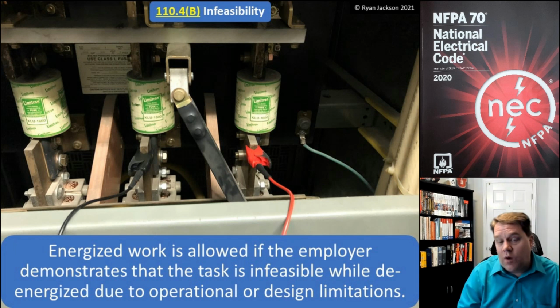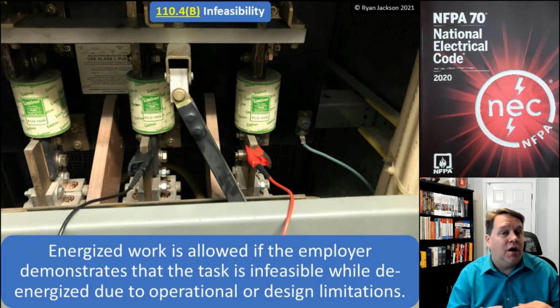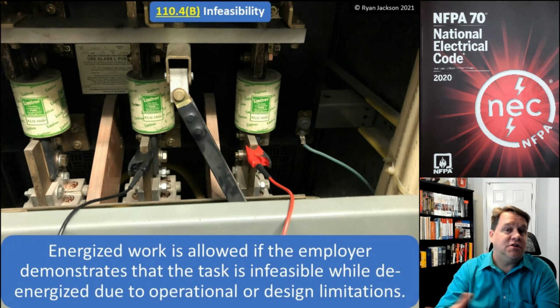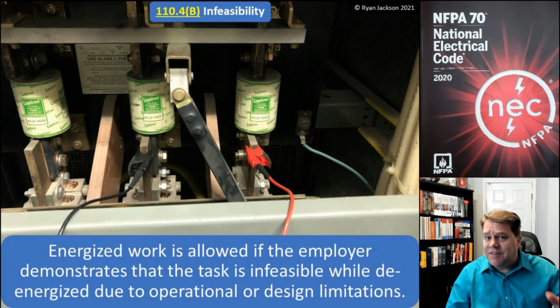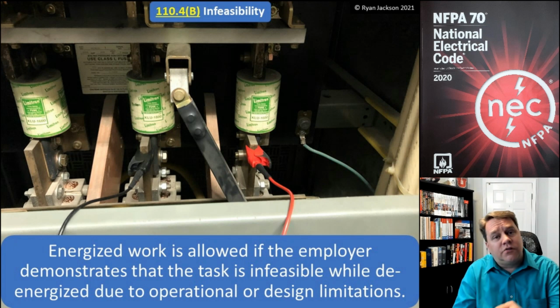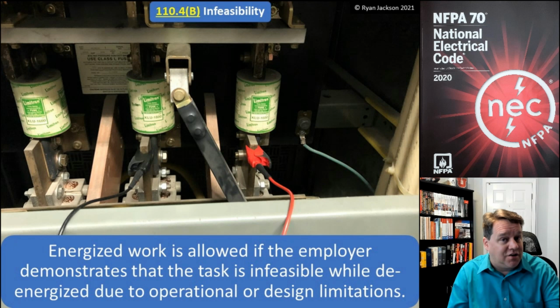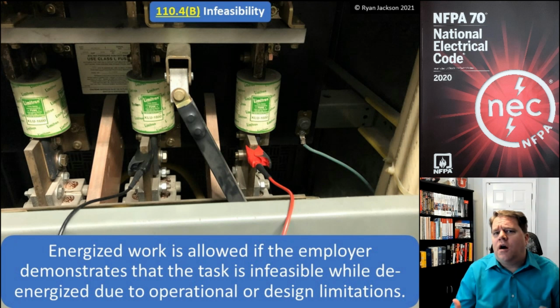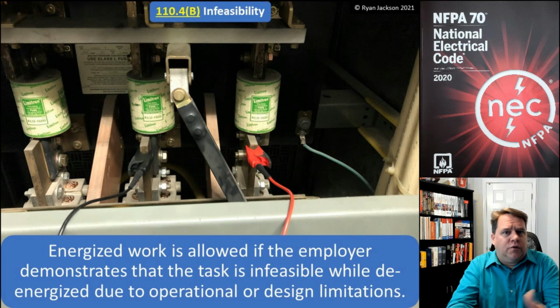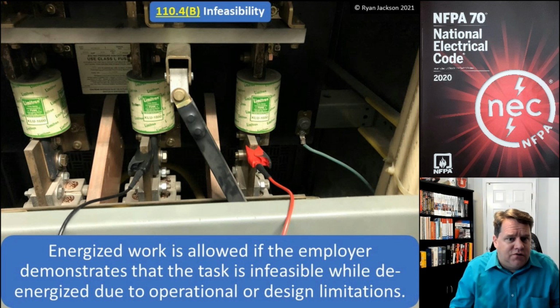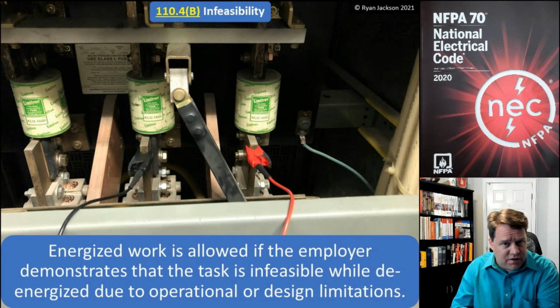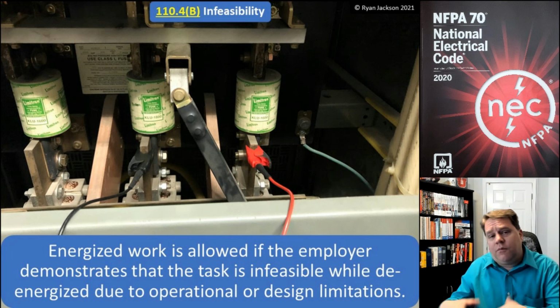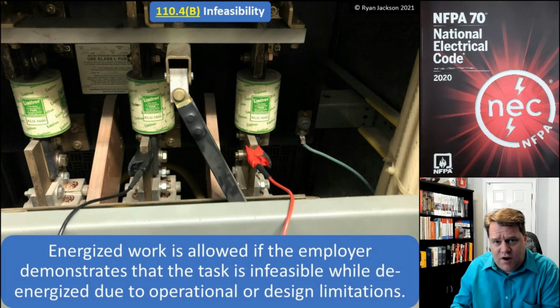And when we look at the Article 100 definition of working on energized equipment, it breaks it up into two different types. It talks about repair on energized equipment, which is where I'm actually going in and physically making changes and terminations and things. That can usually be avoided. The other type of working on energized equipment is diagnostics. And unfortunately, we're not in a position where we can verify voltage without things being turned on. So I think diagnostic is something that we're going to have to come to grips with the fact that it has to be done energized.